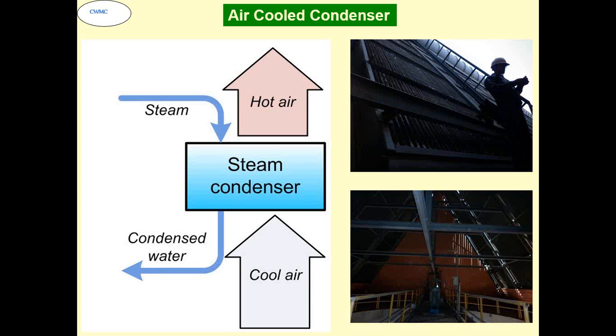The fourth category, which is now coming up, is the air-cooled condenser. An air-cooled condenser does not require much water. It works on the principle of air coming in contact with the heated liquid and cooling it down, and in turn the heat is transferred to the atmospheric air, and the cooled liquid is sent back. The problem is, this is a very large system.